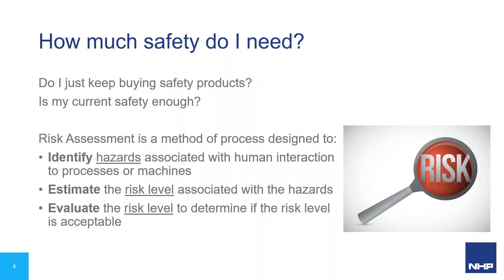As part of any machine life cycle — during design, commissioning, operation, etc. — it's important to perform a risk assessment to determine what you need to do and if it's enough. A risk assessment identifies hazards associated with the machine, estimates how much risk is associated with that hazard, and evaluates whether the risk is acceptable. There's always going to be some level of risk, but it's important to determine whether it's significant.